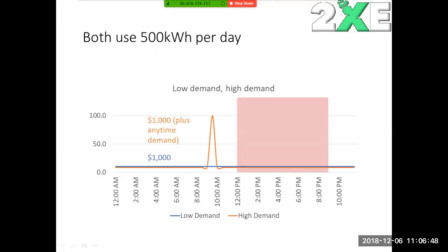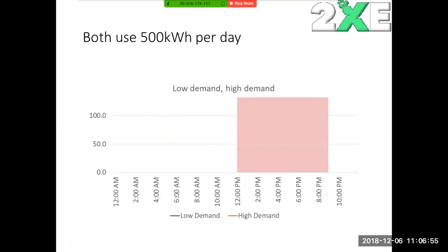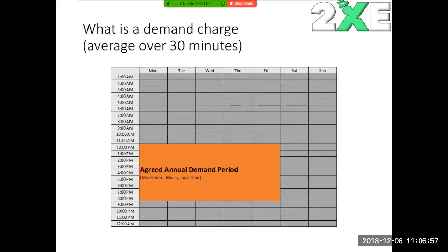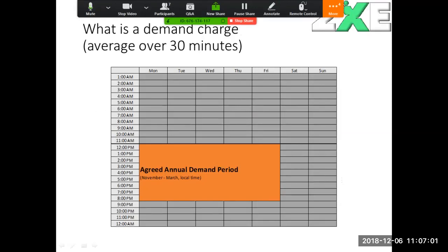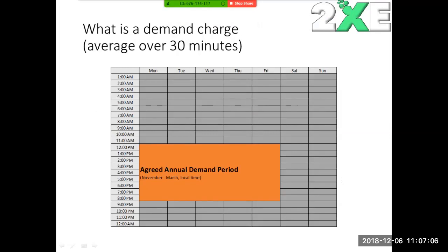Yes, there'll be a smaller anytime demand charge here, but in this system, whenever you reach the maximum demand, that is the maximum demand you're paying for the next 12 months. It's not just a case of this month's electricity bill being higher - you'll be paying those high demand charges for the next 12 months, and that's the minimum before you can request your maximum demand be reduced again.